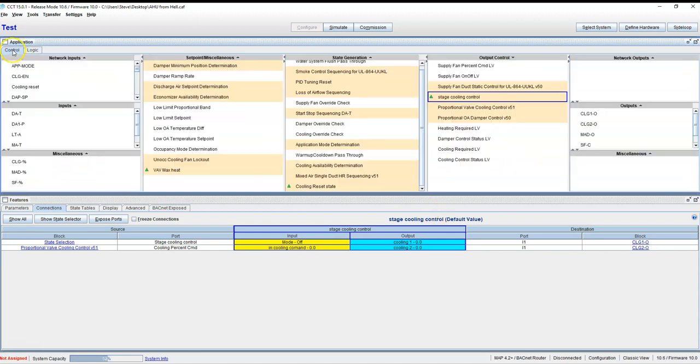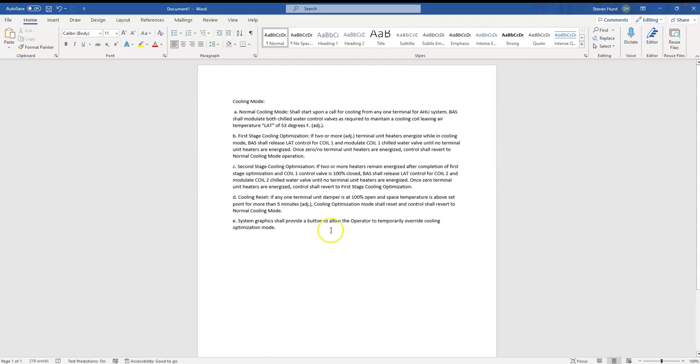I don't know what the engineer was thinking here instead of doing a simple discharge air reset temperature based on this. I'm telling you right now that there's going to be increased humidity from controlling one cooling valve separate from the other cooling valve. But hey, this is what the engineer had in mind, so let's give them what they want.